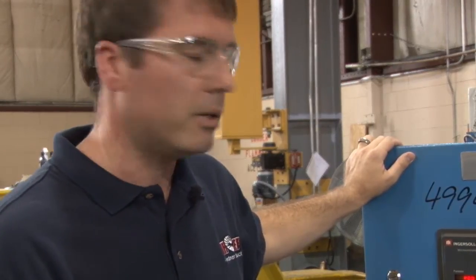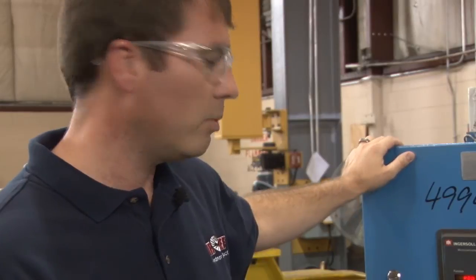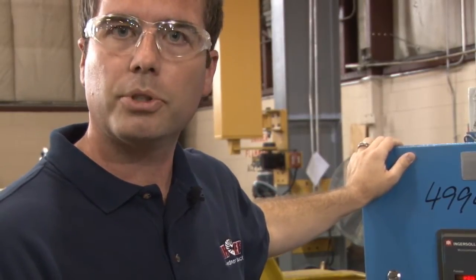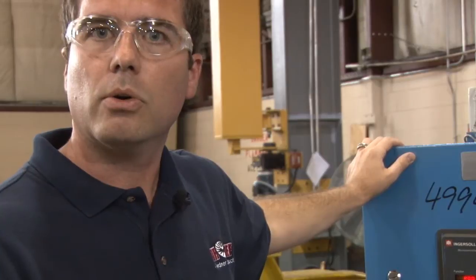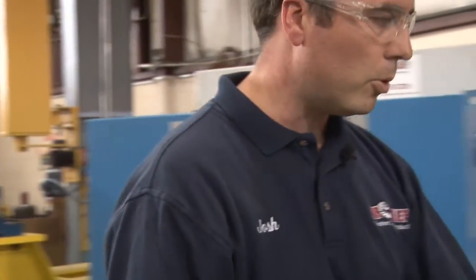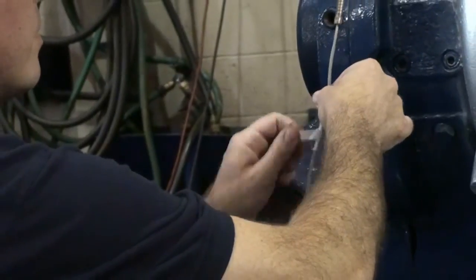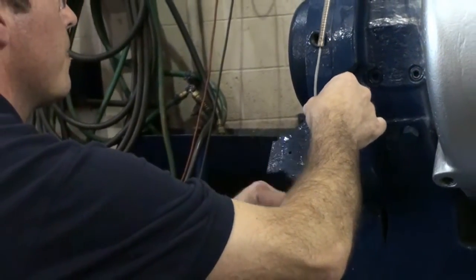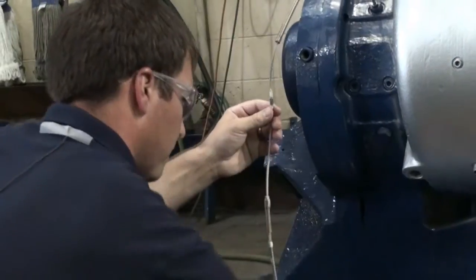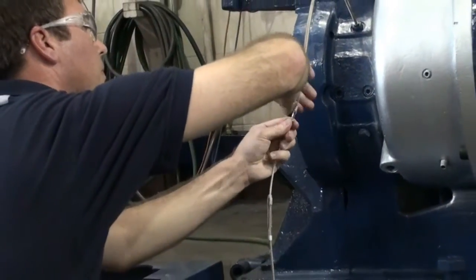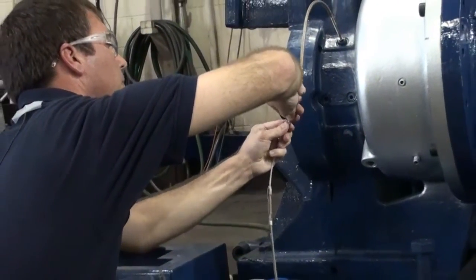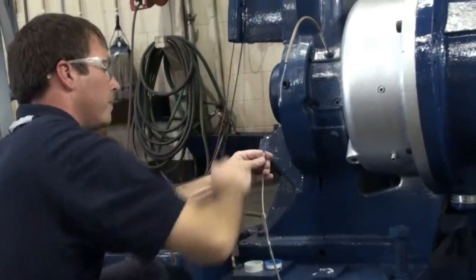The connections are tightened. We would want to come back over. You've rolled the machine by spinning the shaft. You still haven't noticed any vibration trouble. So we did trip an alarm for a reason. So we would, at that point, go to the end of the probe cable where it was connected to the vibration probe itself. Now we want to distinguish whether the problem is in the equipment or the machine itself.